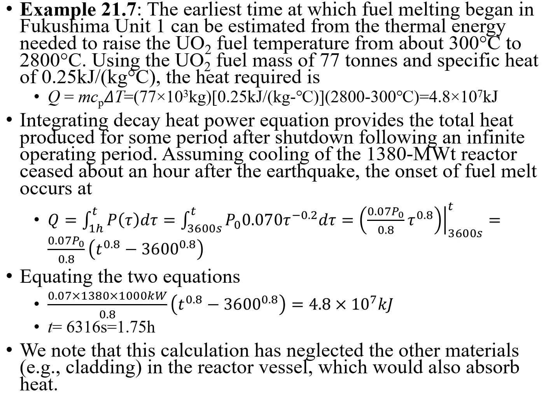And we know that the UO2 fuel mass is 77 metric tons, and the specific heat of this fuel is 0.25 kilojoule per kilogram per Celsius. So the concept is that the fuel is going to produce the decay heat. Then, if the reactor loses cooling, that heat has nowhere to go and is stored inside this fuel. And if you have heat stored inside the fuel, then the fuel temperature is going to increase. The first step is that we'd like to calculate how much heat energy this fuel can store before it is melted.